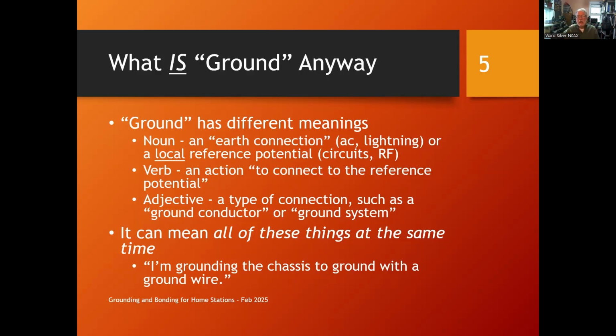And it can also be an adjective to describe a type of connection, like a ground conductor or a ground system. And it can mean all these things at the same time in the same sentence. So you hear people saying things like, I'm grounding the chassis to ground with a ground wire. And all three of those words have different meanings. And you hear people talking about grounding systems, and you listen for a minute, and you realize they're talking about two completely different things, but they're both nodding up and down in the same direction. You've got to watch it.